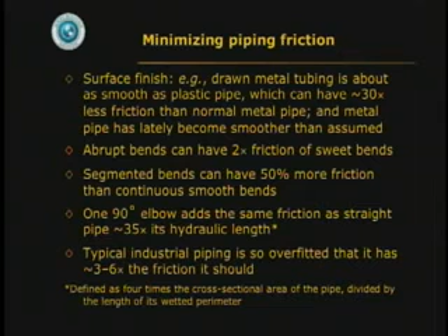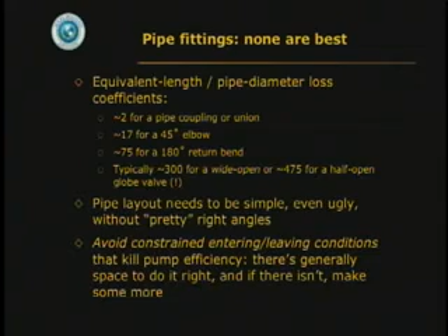Then you can also get rid of fittings. Fittings produce friction. Pipe layout that's pretty will not save money. If it's neat, it's probably not right. And a good way to kill pump efficiency is to have constrained entering and leaving conditions, to scrunch the whole thing up so that there's a bend or a fitting right next to the pump. There's usually space to spread things out and have nice laminar flow going in and out of the pump. And if there isn't, make it. It's worth it.